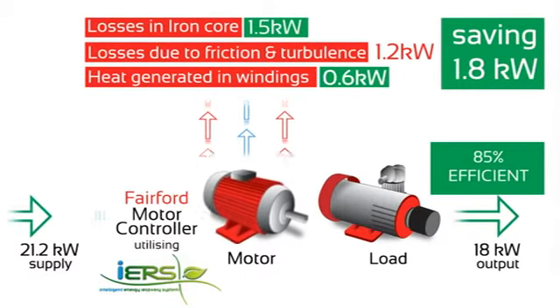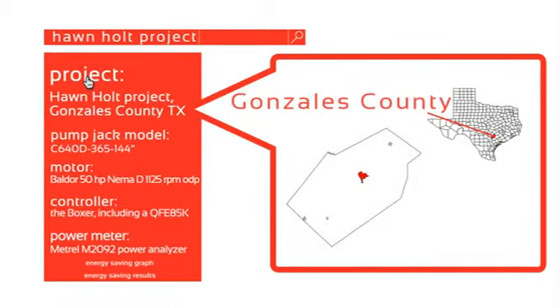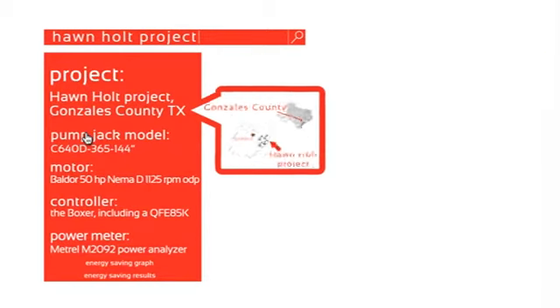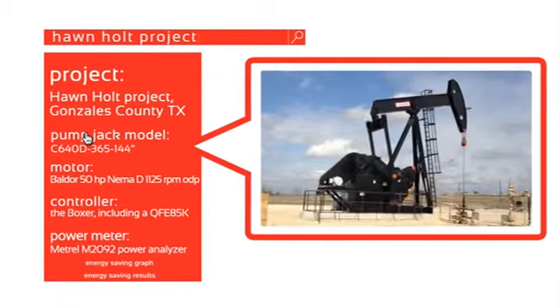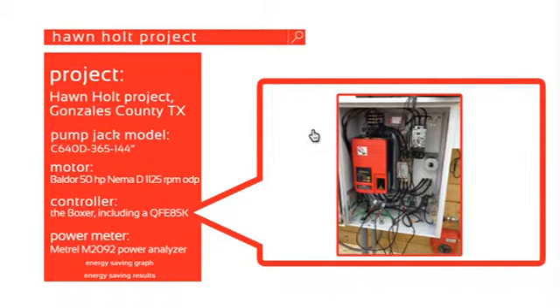Now let's look at a real-world application. In early 2013, a trial of an oil-field pump jack at the Hawn Holt Project in Gonzales County, Texas was undertaken. The purpose of the trial was to investigate the energy saving capability of Fairford's IERS and the Boxer pump jack control system. The Boxer and Fairford's QFE85 were installed on the pump jack's 50hp motor, and the measurements were taken using a Metrel power meter.